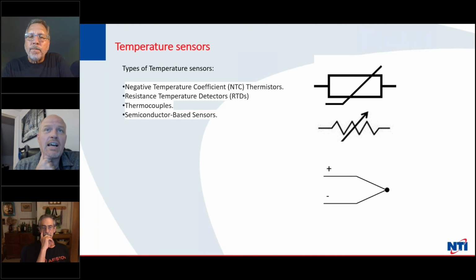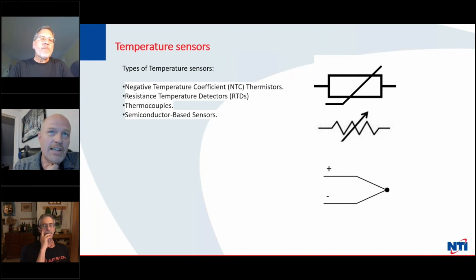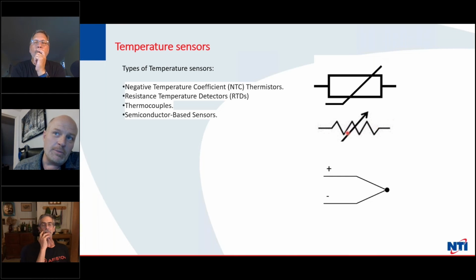Yeah, so temperature sensors. There's a bunch of different types out there that you guys will have come in contact with. Negative temperature coefficient thermistors are the most common thing, by far. They're insanely cheap, they're insanely reliable, and they're basically used everywhere. There's other ones called resistance temperature detectors. The lab would use some of those. Thermocouples, I've got the symbol for each of these. So there's a thermistor symbol at the top, electrically speaking. Resistance temperature detector would be depicted like the center symbol here. Thermocouple would be the one at the bottom.